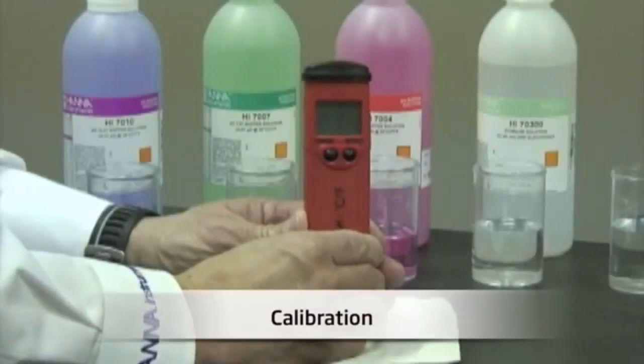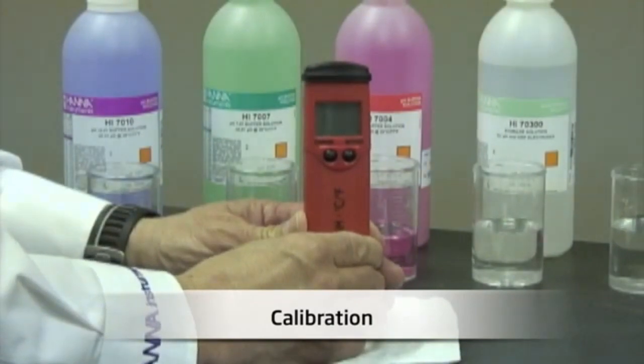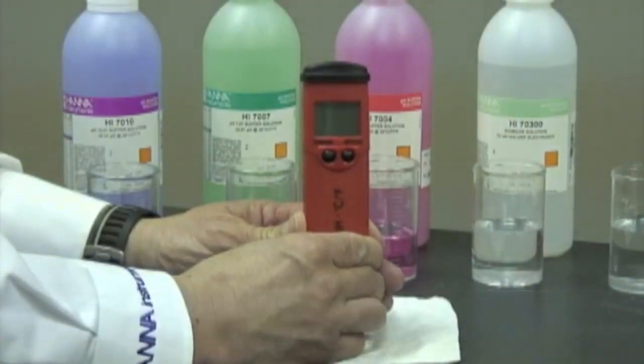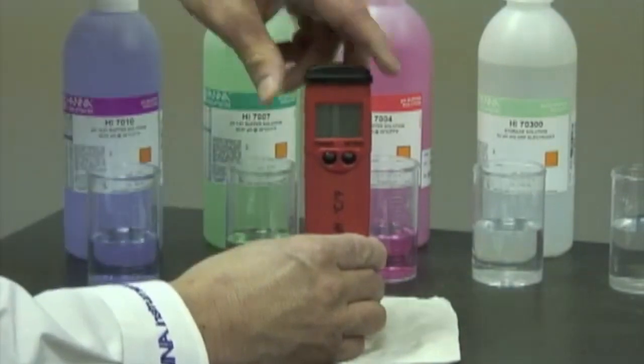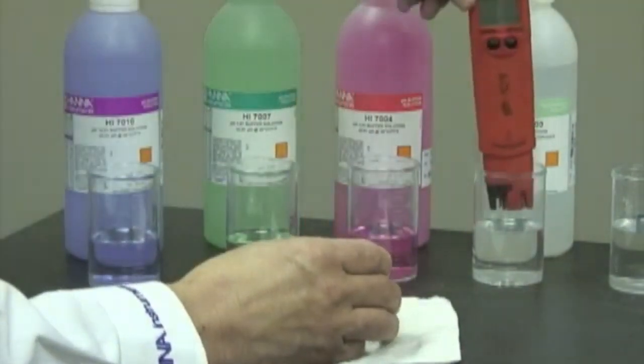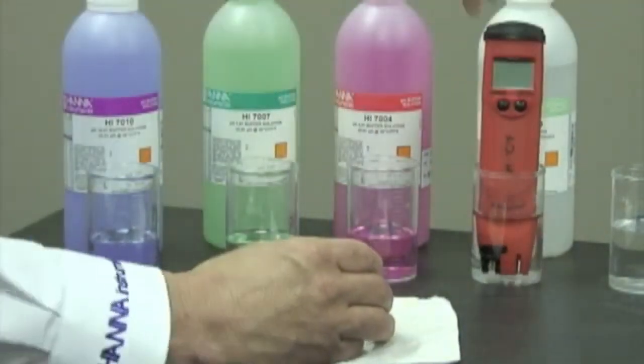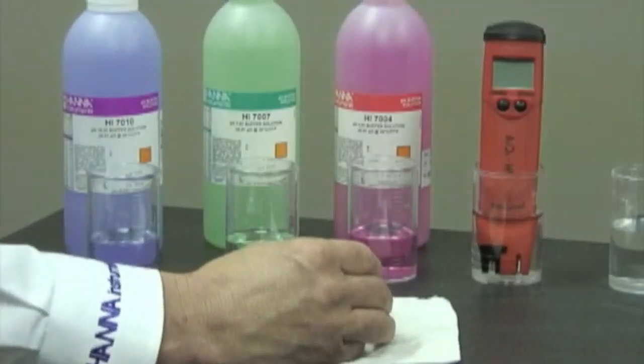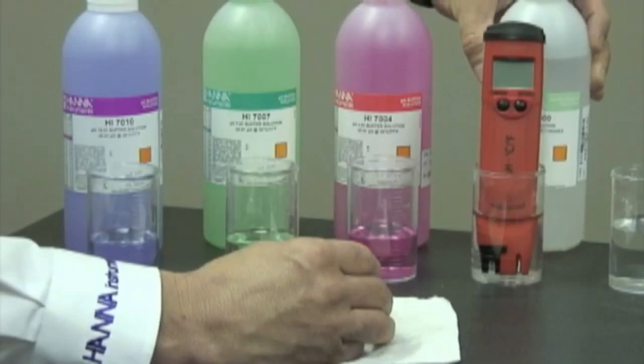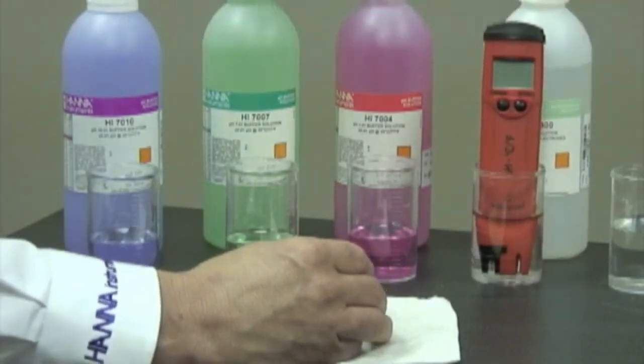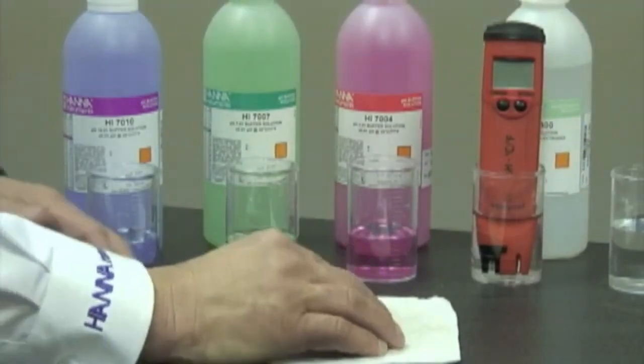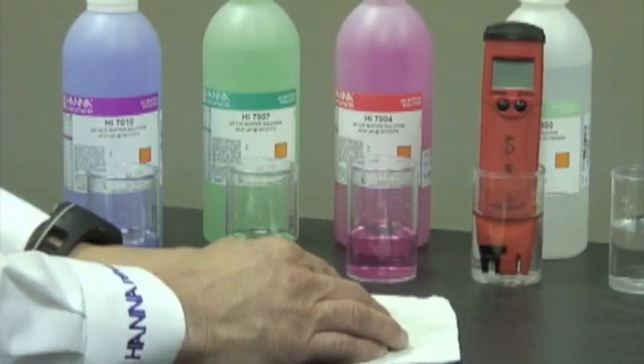Next, let's talk about calibration. Once I remove the meter from the box, it's very important to condition the electrode first. So what I'm going to do is simply take the meter and put it into a storage solution. In this case, it's Hanna Instruments HI70300. If you don't have a storage solution on hand, that's okay. You can use a buffer. I'm going to wait for 2 hours.